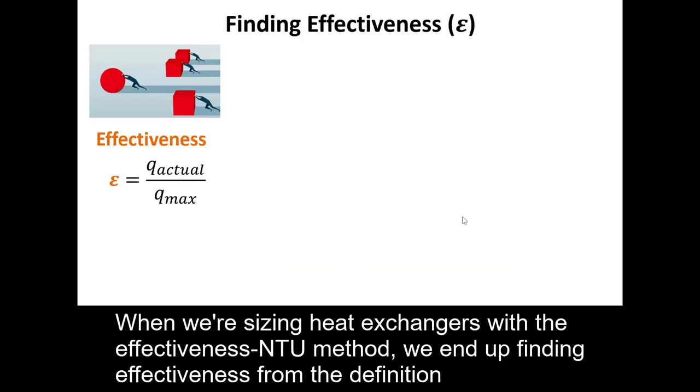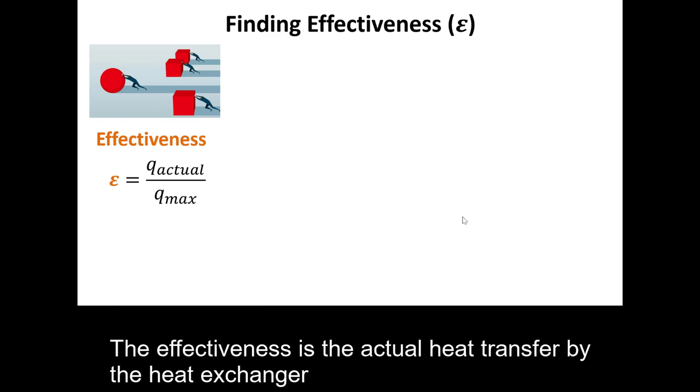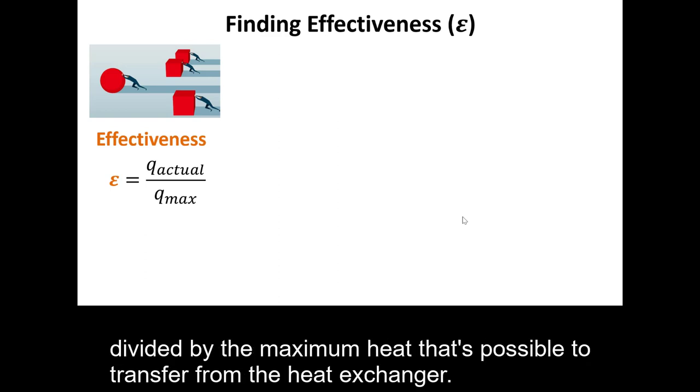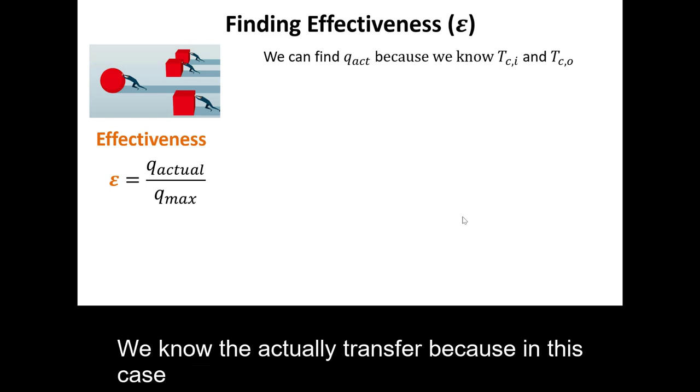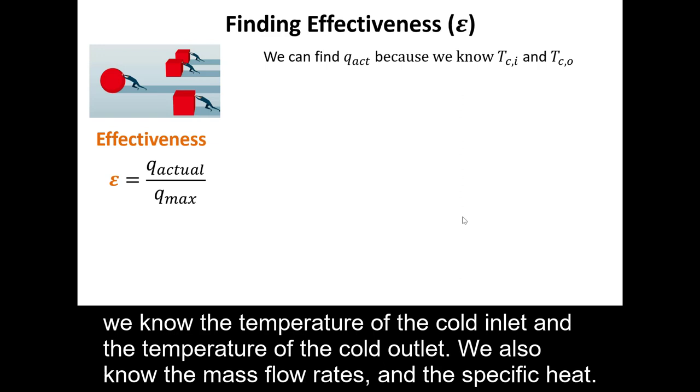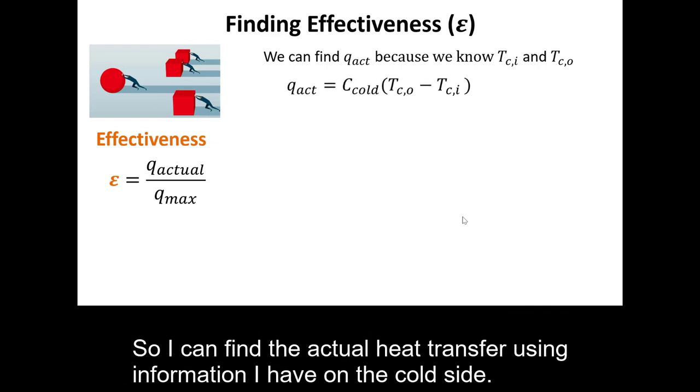When we're sizing heat exchangers with the effectiveness NTU method, we end up finding effectiveness from the definition. The effectiveness is the actual heat transferred by the heat exchanger divided by the maximum heat that's possible to transfer from the heat exchanger. We know the actual heat transfer because in this case, we know the temperature of the cold inlet and the temperature of the cold outlet. We also know the mass flow rates and the specific heat. So I can find the actual heat transfer using information I have on the cold side.